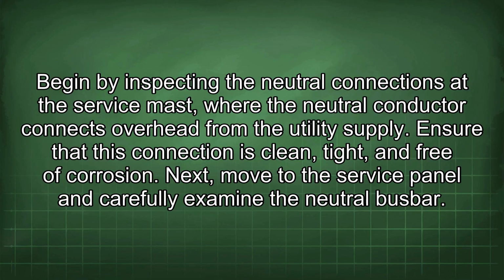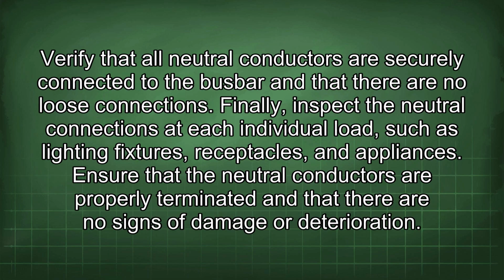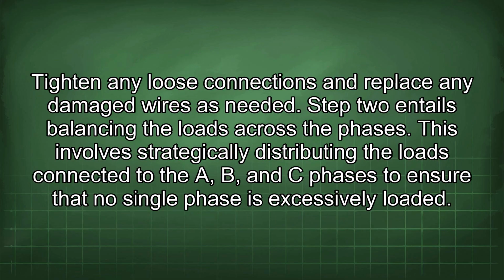Next, move to the service panel and carefully examine the neutral busbar. Verify that all neutral conductors are securely connected to the busbar and that there are no loose connections. Finally, inspect the neutral connections at each individual load, such as lighting fixtures, receptacles, and appliances. Ensure that the neutral conductors are properly terminated and that there are no signs of damage or deterioration. Tighten any loose connections and replace any damaged wires as needed.